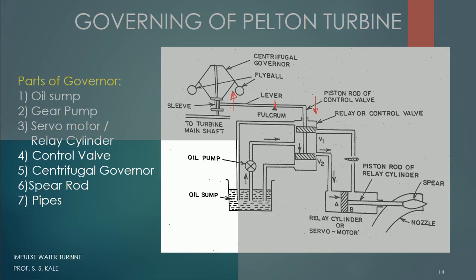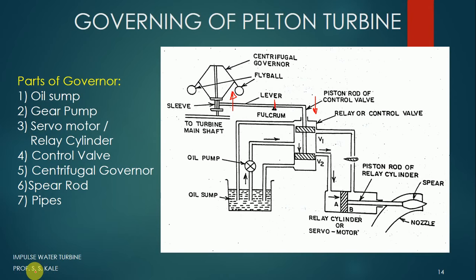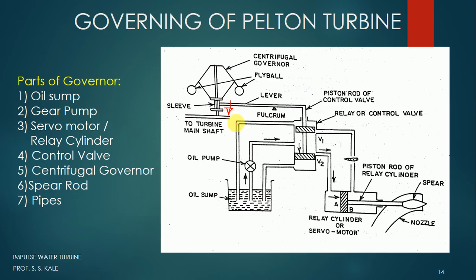Now consider the opposite — the low speed condition. When load on the turbine increases, the speed of the turbine reduces. When speed decreases, the fly balls move inward and the sleeve moves down. As the sleeve moves down, this side of the lever also moves down, and because of the fulcrum, the other side of the lever moves up. When this part of the lever moves up, the two pistons of the control valve also move upward.